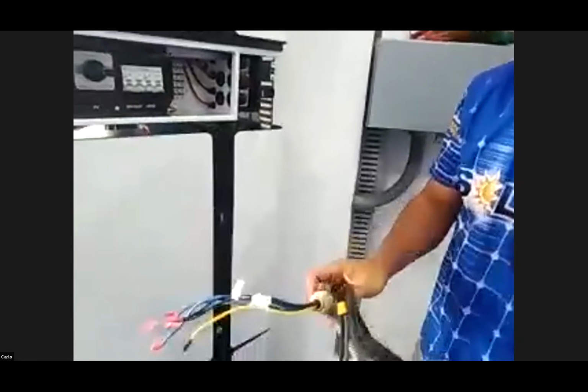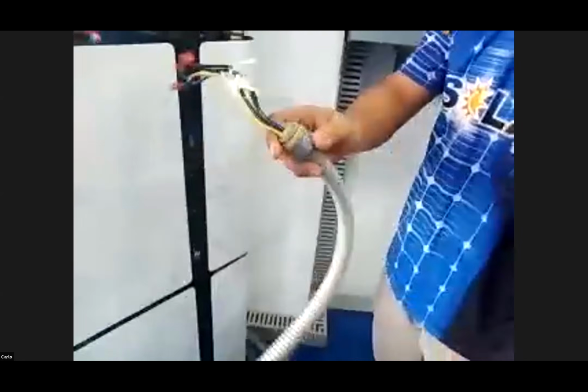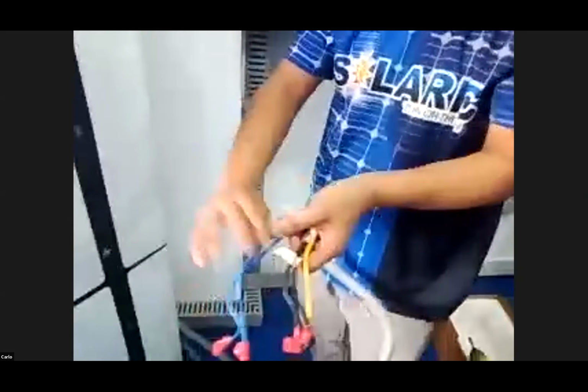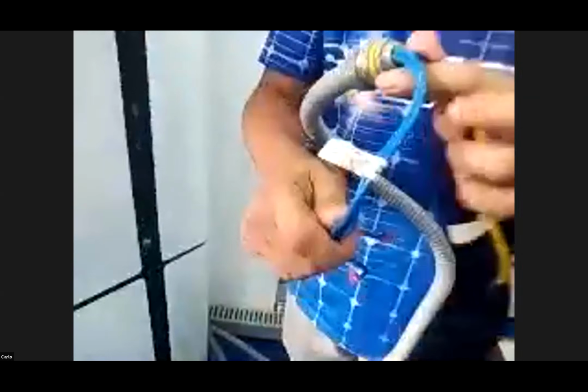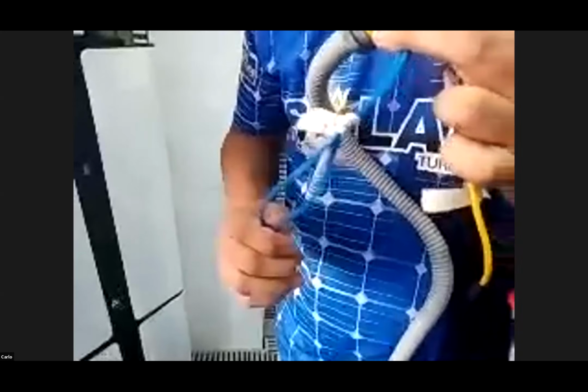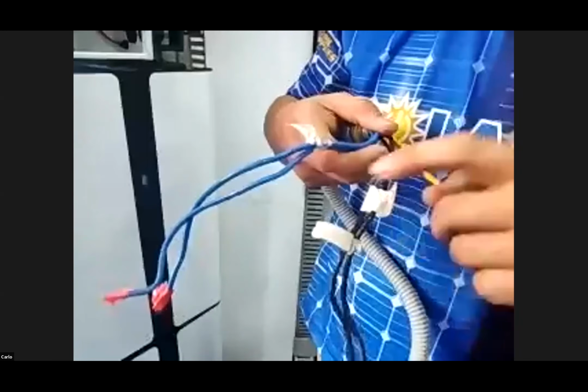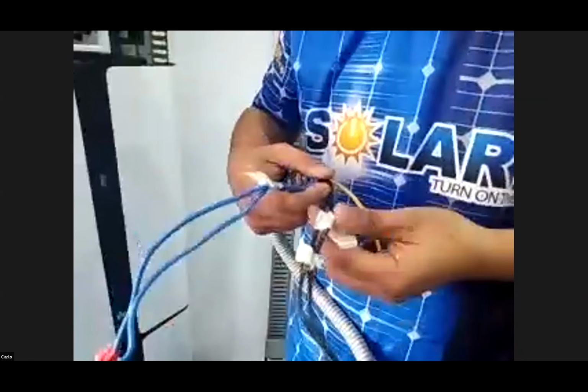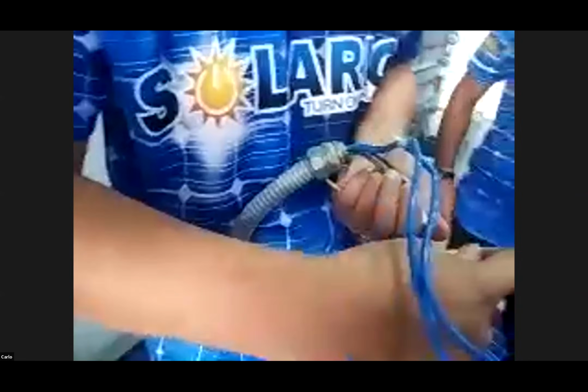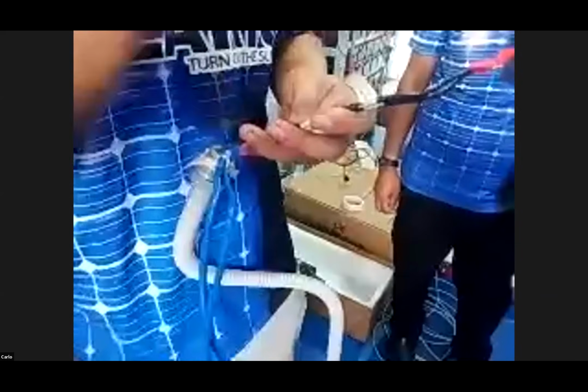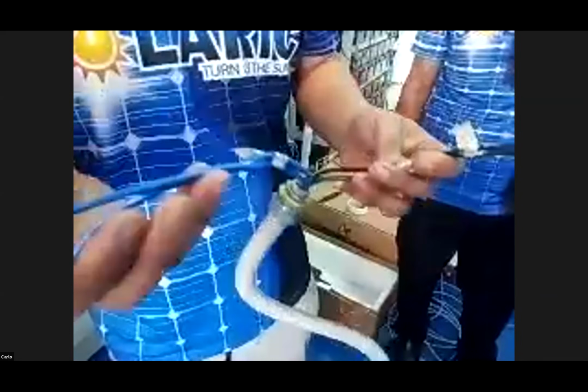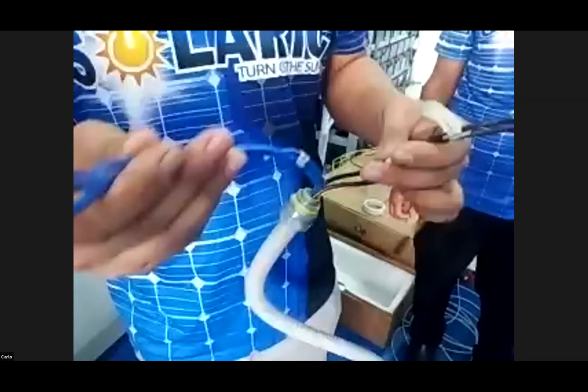For the AC side cable, we need to use at least 5.5 mm squared THHN for the cable. JR, show it. The right one is for the grid and the other one is for the backup. Backup means the output of the inverter - it will be the load supported by the batteries during a power outage.